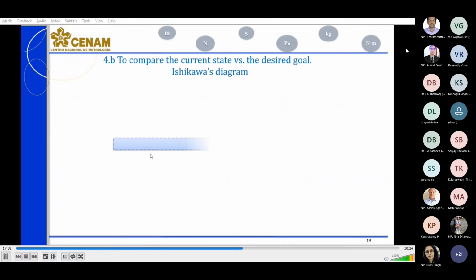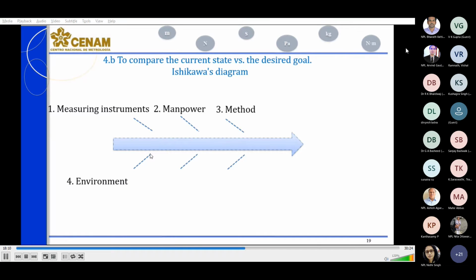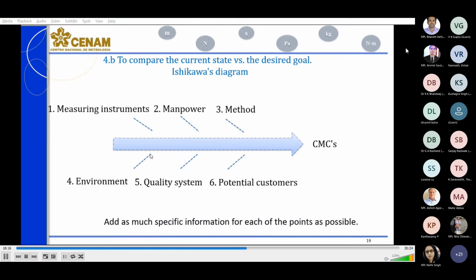We move to 4.B, which is the comparison by means of the Ishikawa diagram. The Ishikawa diagram is the cause and effect, and we can put 6 points there. The first point, we can use measuring instruments. Second point, manpower. Third point, the method. Fourth point, environmental conditions. Fifth point, quality system. And sixth point, potential customers' requirements. Then, for each of these points, we should add as much specific information as possible. And all of this, the idea is that we can increase or improve our CMCs.